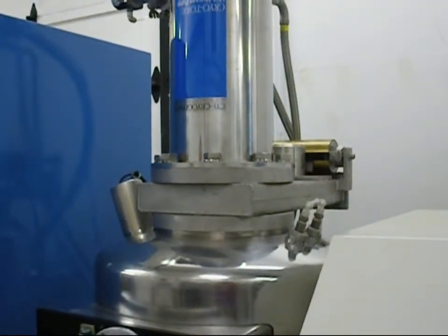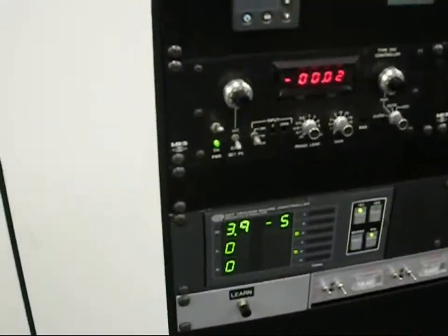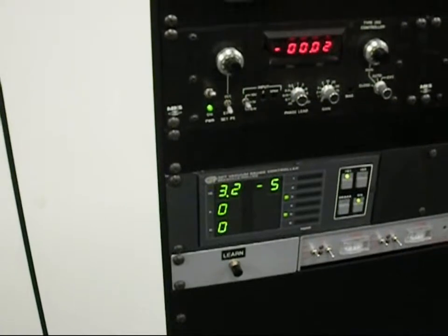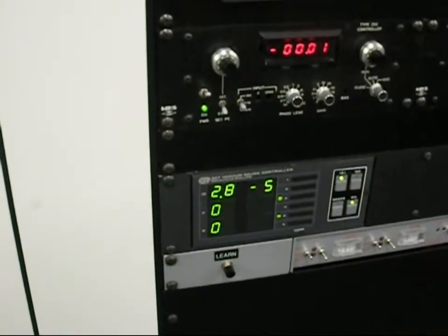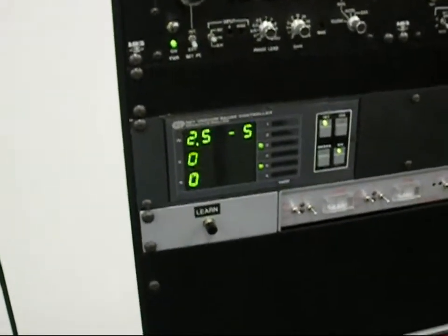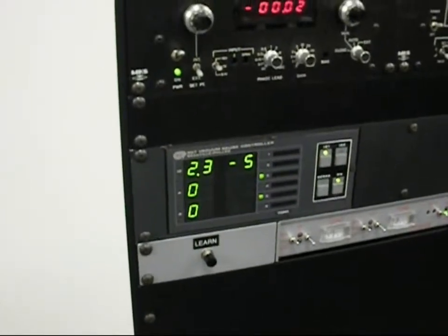Once the load lock chamber high vac set point has been achieved, the load lock chamber is ready to initiate a pallet exchange between the load lock and main process chambers. The pallet exchange sequence can now begin.